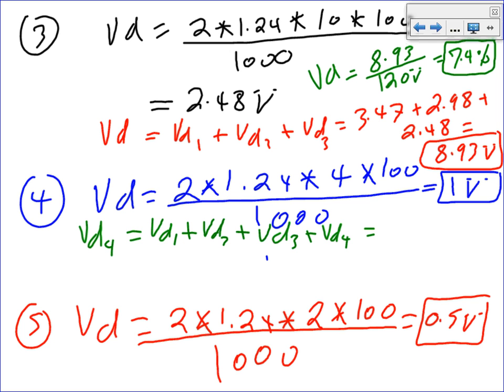The voltage drop, if we were calculating number 2, did we ever minus the voltage that we lost? You can do that to find the operating voltage. So if I ask you what's the operating voltage at 3, you subtract all the voltages that we lost at 3 from 120, that'll get you the operating voltage at 3. And that's what we're doing, right? The operating. Subtract all the stuff that you lost at 3, 2, and 1 from 120, that'll get you the operating voltage at 3. Right. All right, what's this one, guys?